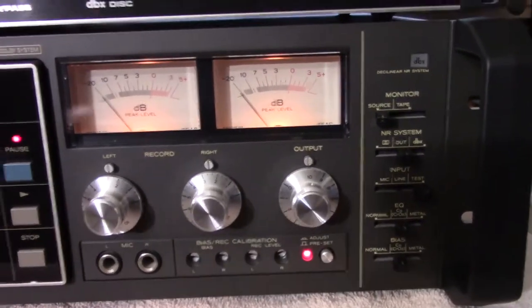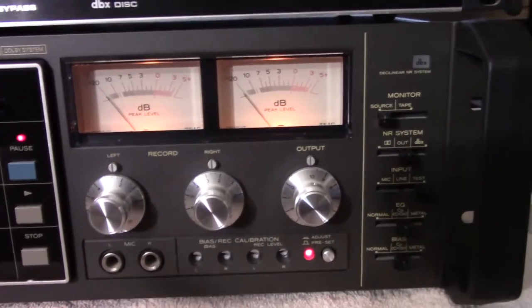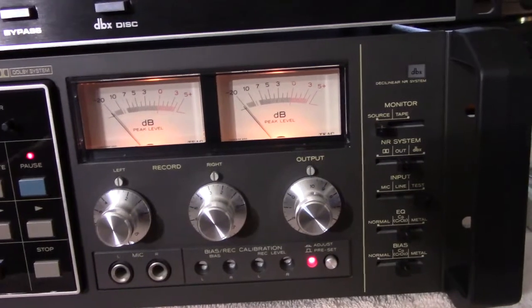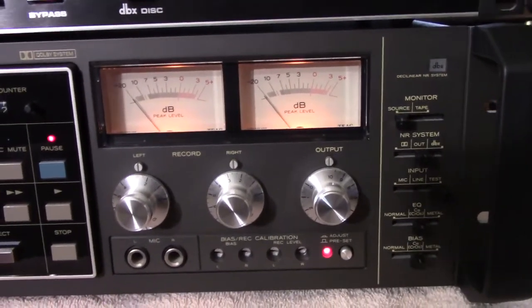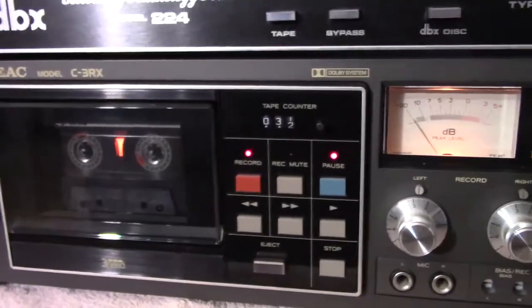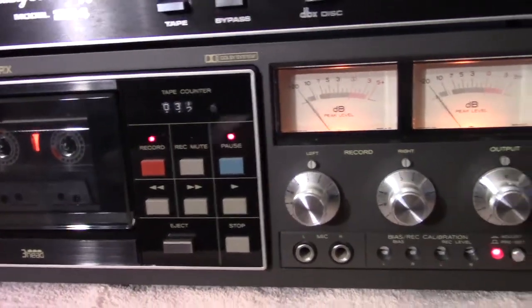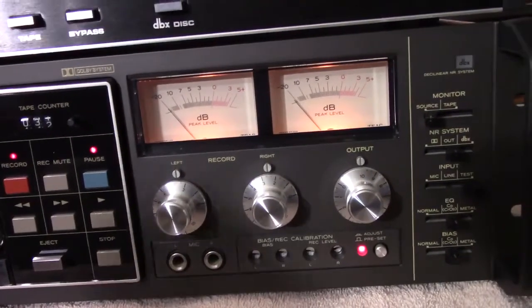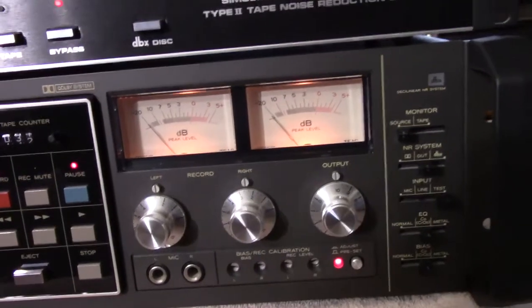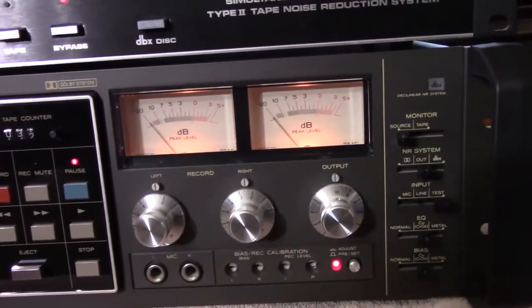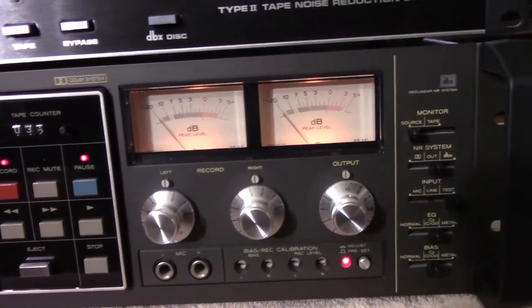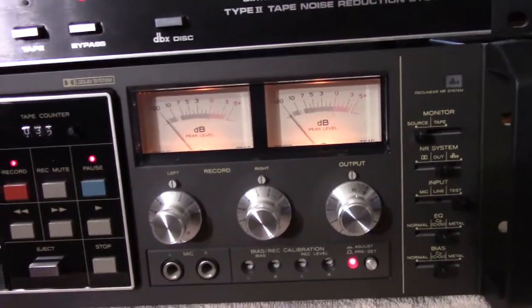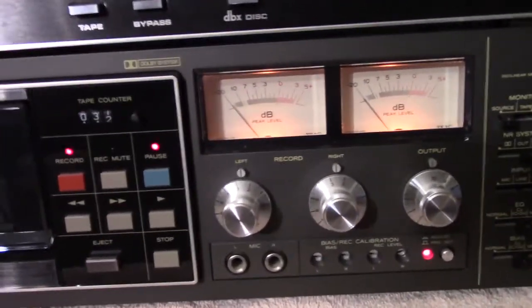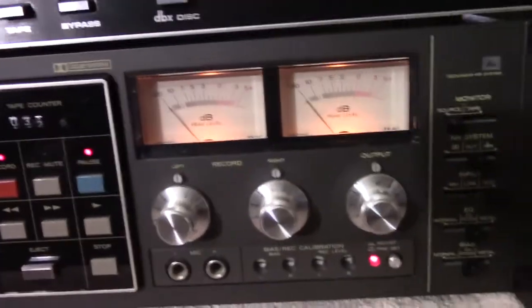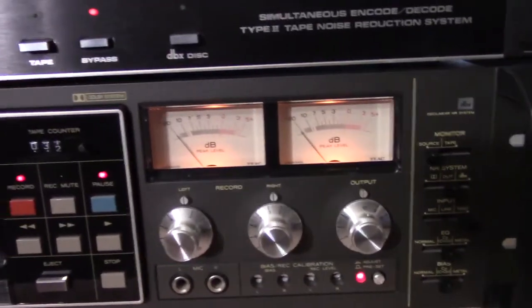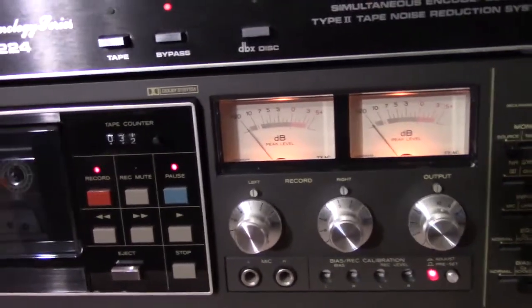That's how I got my tones. I went to a website, I forget which one, but it's a tone generator website, and you just tell it what frequency you want, and it will let you record it. Okay, so I got a 400 hertz tone and a 12.5 kilohertz tone. I went into my SoundForge and altered them until they were exactly the same level, dB-wise. Then I put it onto a little SD card into my MP3 player, which is also a WAV file player, and that's what I've got going into this guy now. It's going to play, and I'm going to calibrate this guy with that tone.